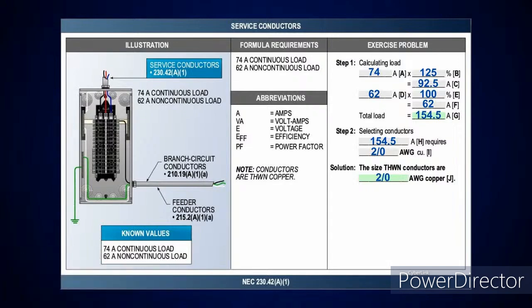Now, if you look at this, this is a service. Remember what I told you last week: it doesn't matter if I'm doing a service, a feeder, or branch circuit, you always take the continuous loads at 125% and non-continuous at 100%. The only thing that's different: for services, I'm in 230.42(A)(1). For feeders, I'm at 215.2(A)(1) and 215.3. For branch circuits, I'm in 210.19(A)(1)(a) and (b), and also 210.20(A). Okay? So let's look at it.